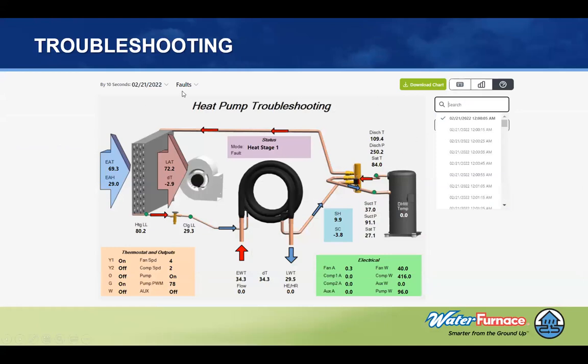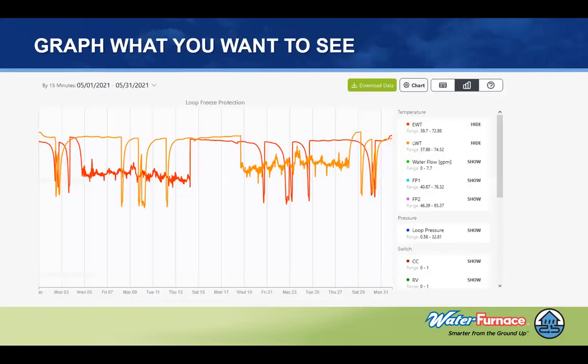You can also go from your fault directly to the time of day and then go to this troubleshooting form that I showed you before that allows you to know that troubleshooting. From a graphing standpoint, we have all the parameters that you can graph, and I then say, okay, I think I have a water flow problem on my system. I can then go in and hide everything with the exception of the water flow parameters, entering and leaving water temperature, and I can then dial into exactly what's going on with and when the problem occurs from that aspect as well.